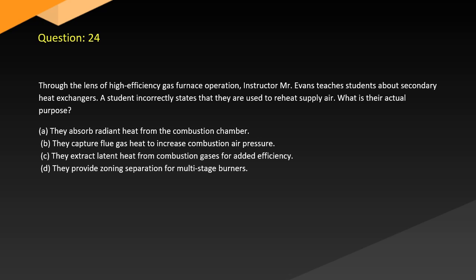Question 24. Through the lens of high-efficiency gas furnace operation, instructor Mr. Evans teaches students about secondary heat exchangers. A student incorrectly states that they are used to reheat supply air. What is their actual purpose? A. They absorb radiant heat from the combustion chamber. B. They capture flue gas heat to increase combustion air pressure. C. They extract latent heat from combustion gases for added efficiency. D. They provide zoning separation for multi-stage burners.